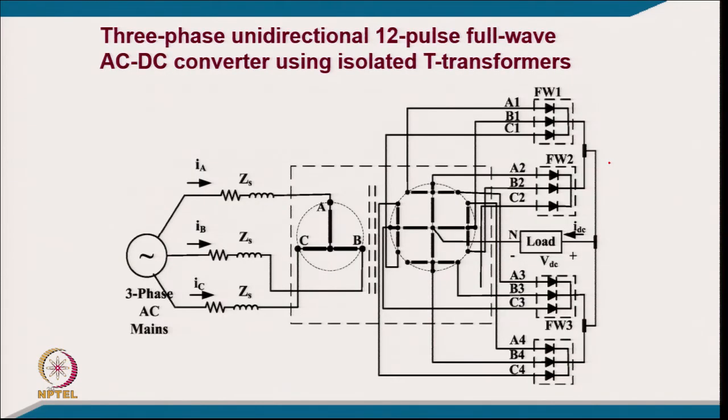And then you can have even the T connection for 12 pulse, which you design with the proper geometry as the circle voltage. All 12 points of supply should be on the same circle, so that you get the same RMS voltage at the output with respect to the neutral point, from the primary side as well as the secondary side. Normally the neutral is somewhere else, but we do not need it on the primary because it is a 3 phase supply; on the secondary we need the neutral to connect the load. So from this neutral or center point, if you take all the vertices, they will be equal and you will have what we call the 12 phase supply here.